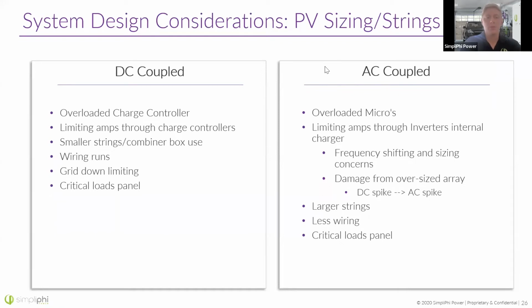You're able to combine PV runs with combiners. Now this can be a little bit of a hassle, to be honest, when you have multiple strings coming off the roof and needing to use a combiner is an extra part to throw into your system. So keeping those wire runs short and just keeping wires to a minimum is always to your advantage. This is another reason AC coupled systems are popular, because you can have larger strings and less wiring in general.